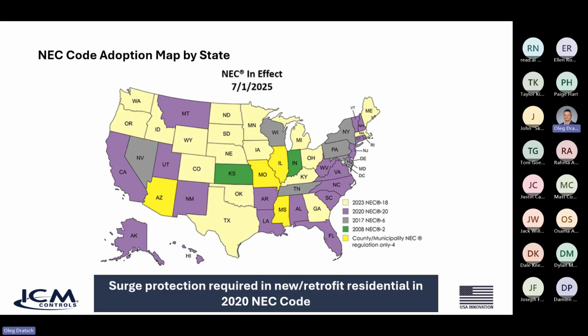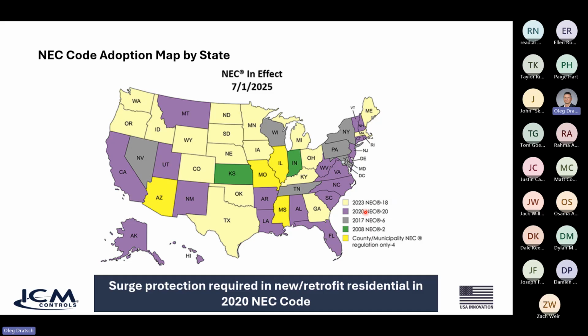So this is the NEC adoption map. The 2020 version is when the NEC started requiring surge protection in new residential construction and retrofit. So 2020 and 2023. If your state is one of those states that's purple or light yellow, that is now a requirement. So it's a pretty easy upsell in those states. Now, states like New York, Pennsylvania, Wisconsin, Nevada that are on the older edition of the code, Tennessee included, are working on getting up to the 2020 code most likely next. I know New York State is. And so it's only a matter of time before it becomes a requirement in those states as well. So it's something to get ahead of, get educated on, and be prepared for.